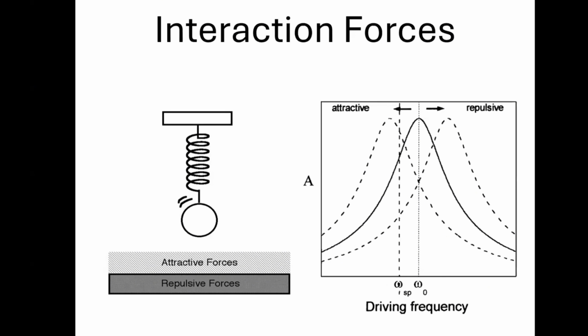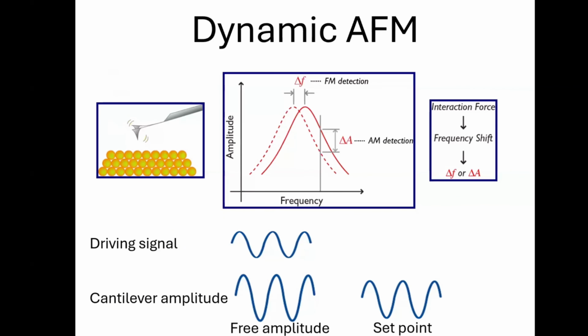These shifts are shown visually here. Generally, you want to operate in the repulsive regime to get nice images in amplitude modulation mode. So as we've been discussing, as the oscillating probe approaches the surface, there will be an interaction force that causes a frequency shift. In amplitude modulation, we stay at a particular AC voltage frequency. And so when the cantilever frequency shifts, there will be a change in amplitude at our drive frequency. We will use this change, typically a reduction in amplitude, to determine our set point for imaging.